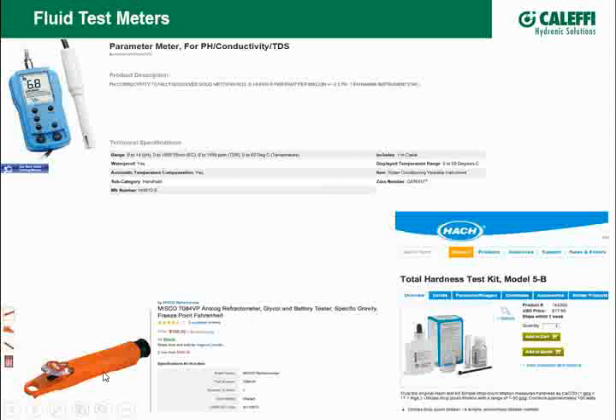For testing glycols, I like this. It's called a refractometer. It's a very simple thing to use. You just put a little drop or two of the glycol here. You close this little trap door on here, and when you close that and push down on this with your finger, it actually turns a light on inside here, and then you look down through the end of this like you're looking down through a scope or a sight glass. Most of them will read both ethylene and propylene glycol. On one side will be PG, on the other side will be ethylene glycol, EG. And they'll tell you the freeze protection rate.